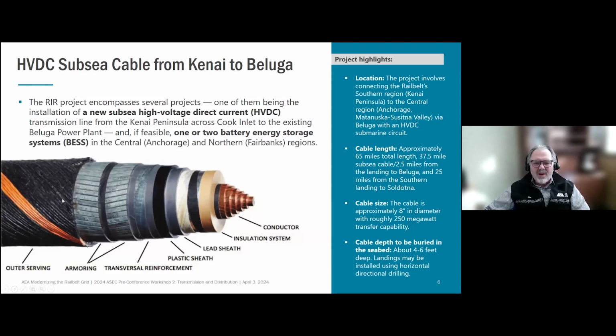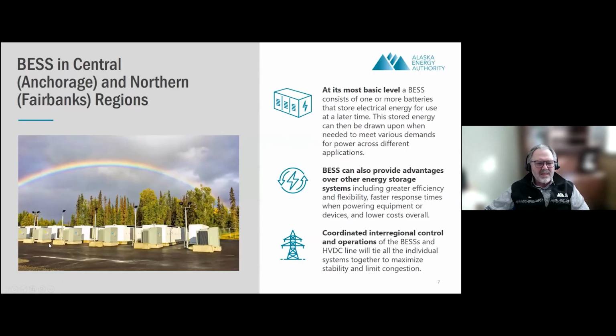Also part of the project, if feasible, were the two BESS systems. This photo is actually the storage system that Homer's put in, and they have lots of what's basically a battery set. They use those for standby. If the generator goes down, you can draw the power off of these. You don't have to keep one of your turbines running at low capacity to be immediately able to pick up the power, so you have plenty of time to start up. If it takes 15 or 20 minutes to start up a turbine, these batteries will hold it, so you're not basically having a turbine idling away and burning up fuel.